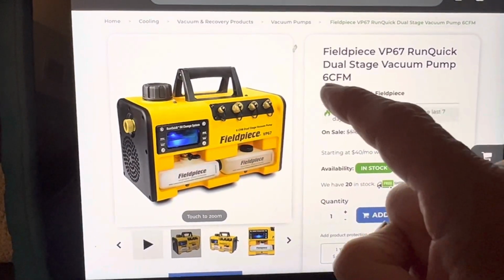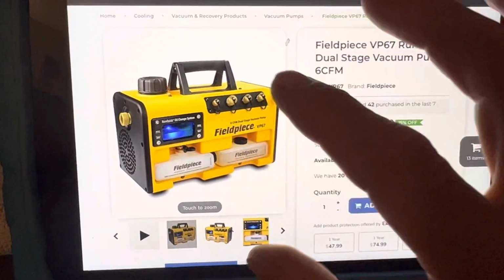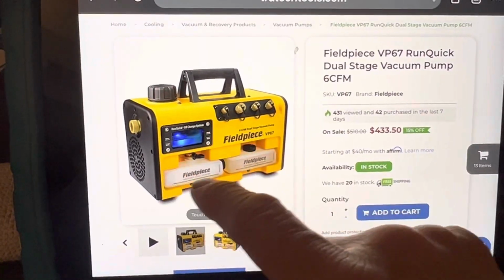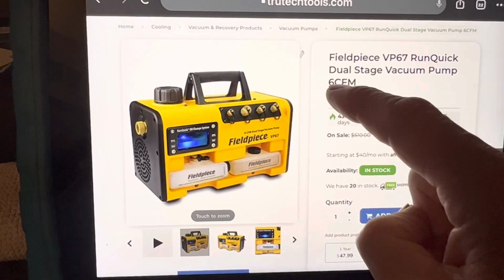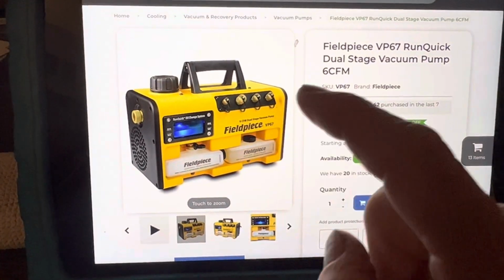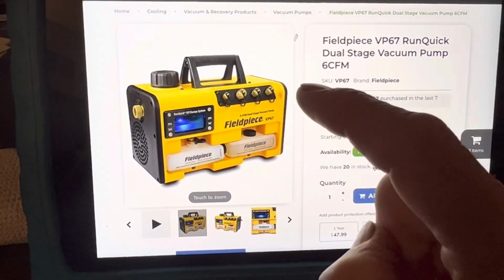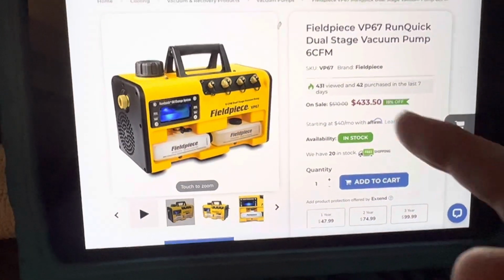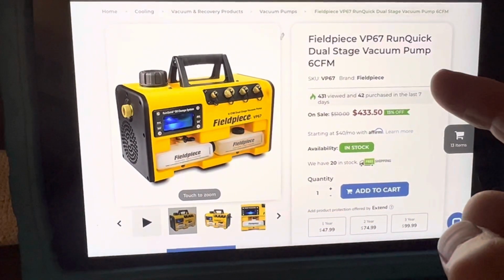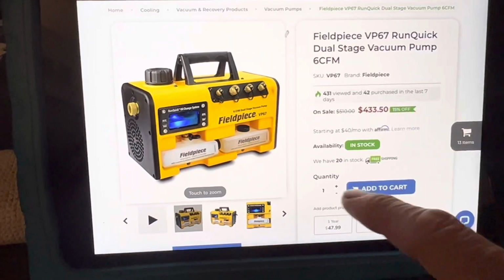It's more important, if you want to save money, that I'd rather see you get a smaller vacuum pump, even a 4 CFM or 3 CFM, and get the blue silicone vacuum rated hose, than spending more money on a bigger vacuum pump. But here's the minimum right there.